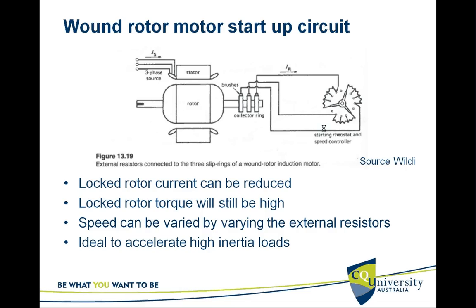By doing this, at startup you can have a high rotor resistance by putting the startup settings to high resistance mode. The locked rotor current can be reduced, and the locked rotor torque will still be high because of the high rotor resistance.